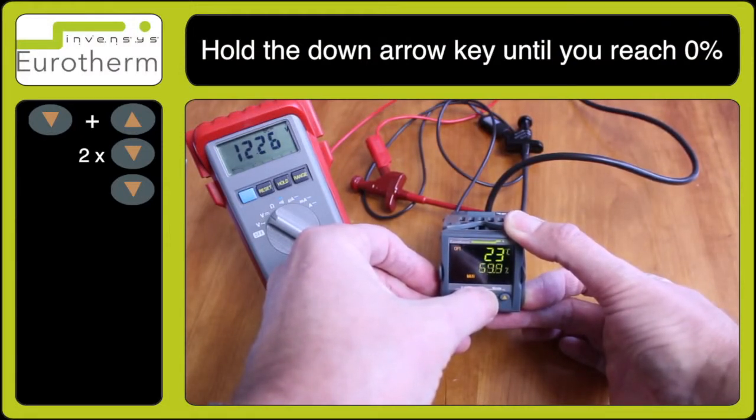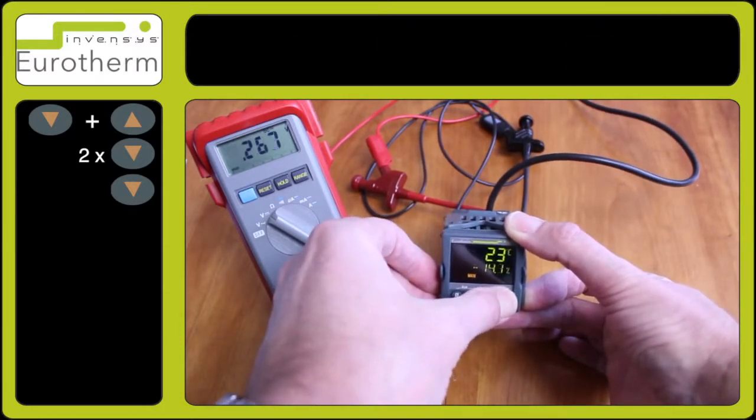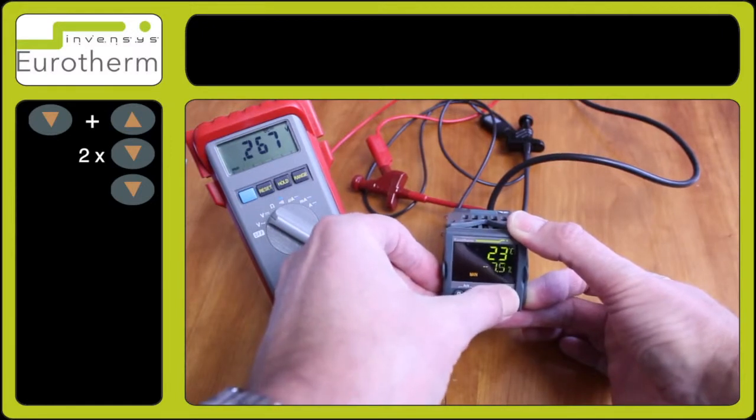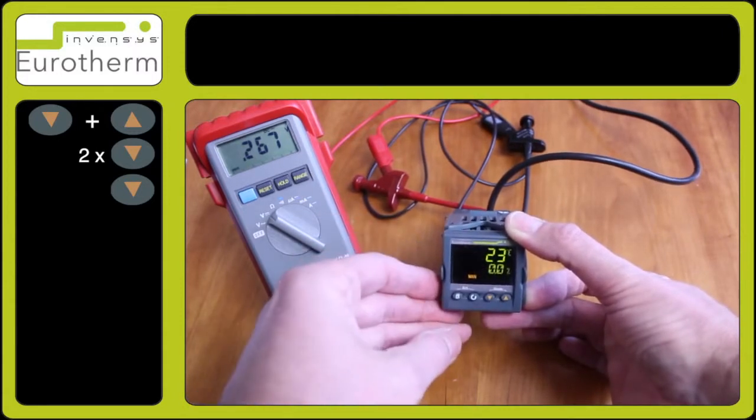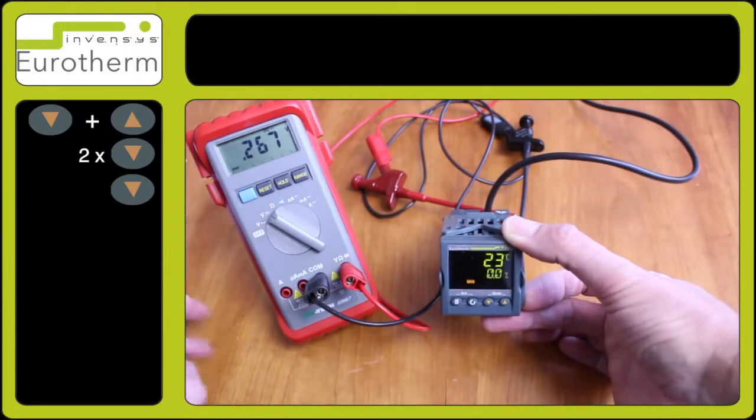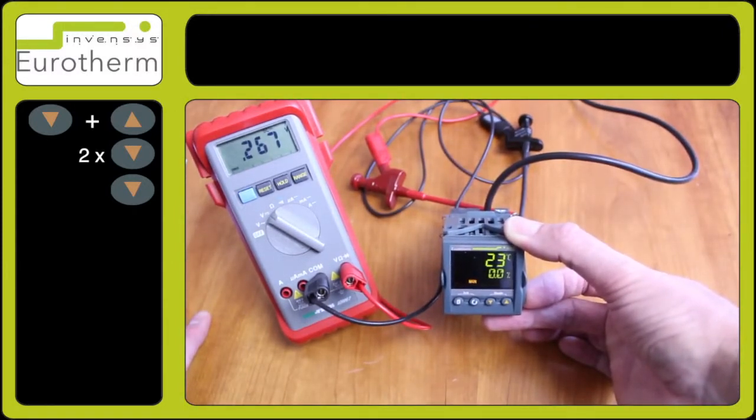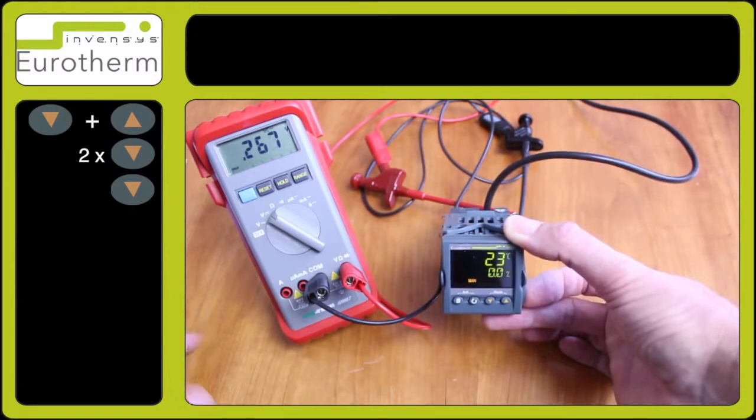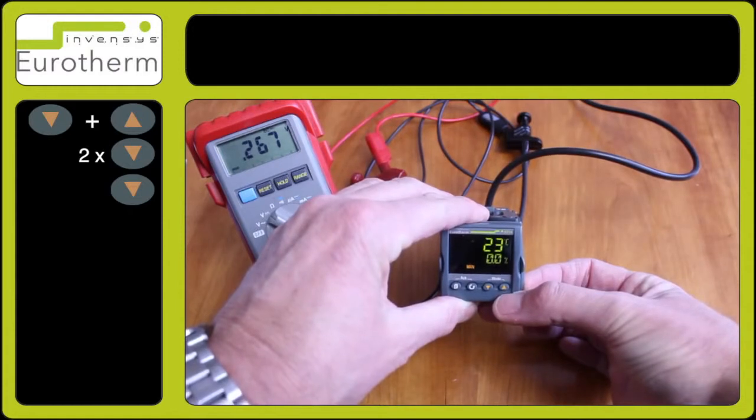The logic output has now collapsed and gone to 0.2 of a volt which means that this particular output is functioning correctly. To return back to your auto selection press the two arrow keys together and reselect auto for normal operation.